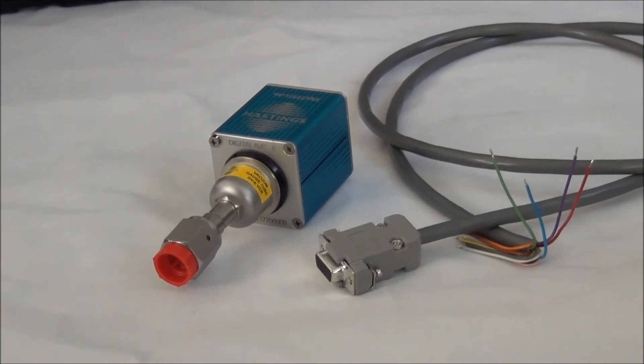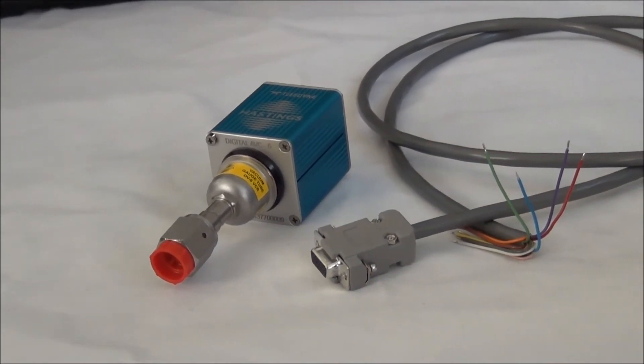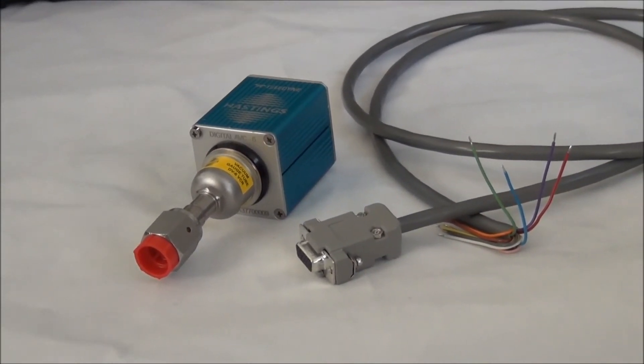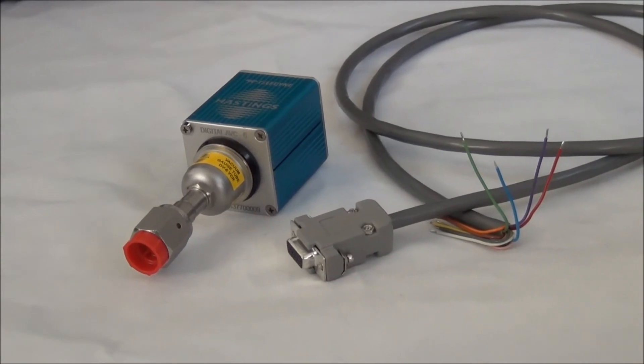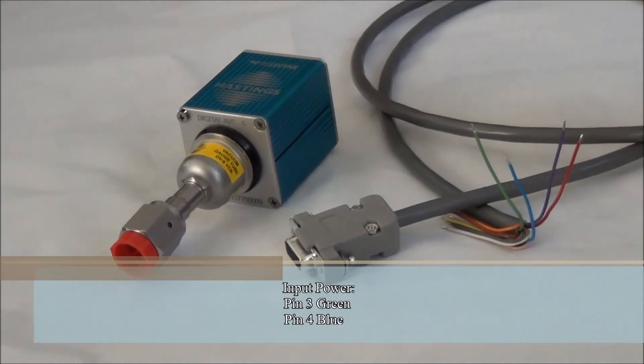Now in our example, we're just going to use four wires: two to bring power in and two to bring back the linear analog output. To feed the 24-volt, we need pin 3, that's the green wire, and the power common is pin 4, that's the blue wire.